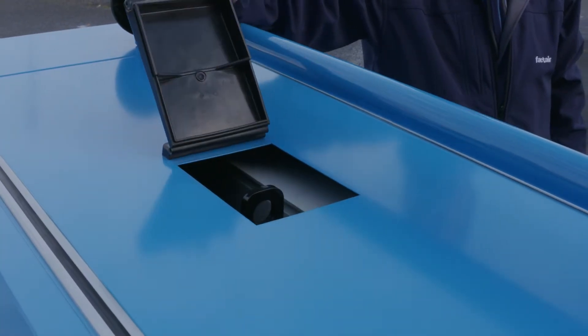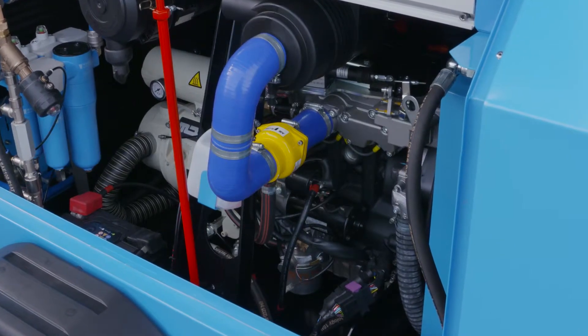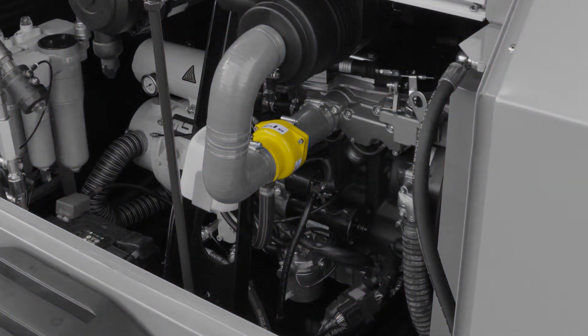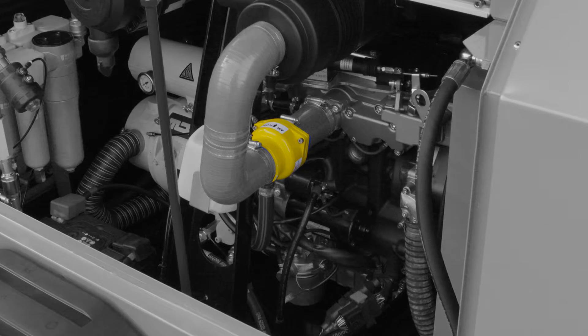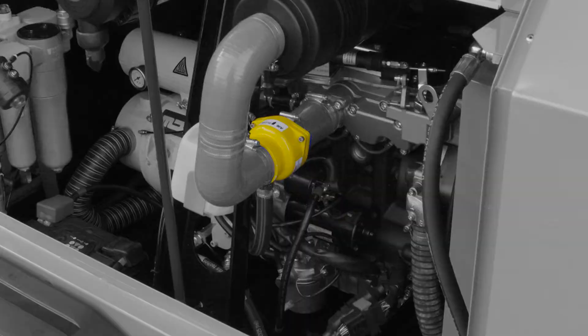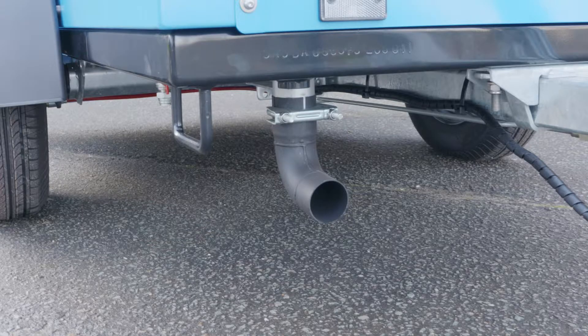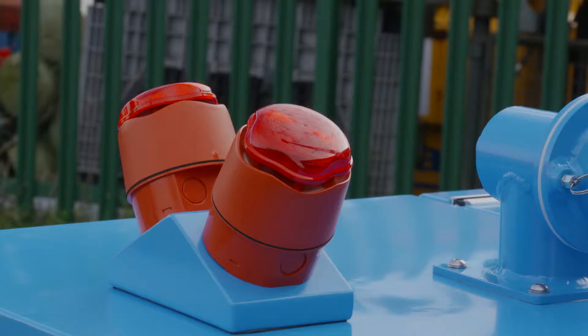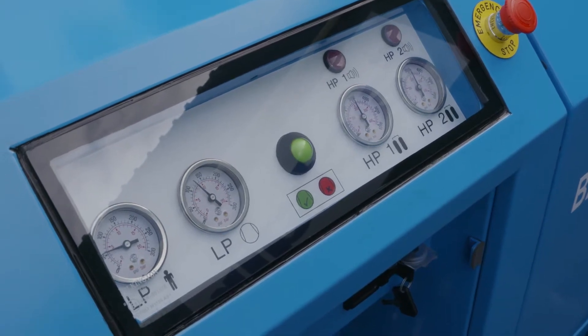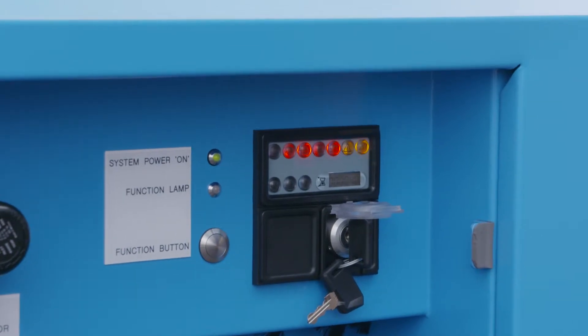A central lifting point is also provided for craneage purposes. The BA800D is fitted with a variety of safety devices. These include a Chalwyn overspeed valve, which shuts off air to the engine should combustible gases be ingested causing the engine to run at excessive speeds, and a spark arrestor which forms an integral part of the exhaust system. There are various audible and visual warning devices incorporated within the compressor, which monitor the high pressure and the low pressure systems, automatically activating in the event of a fault.